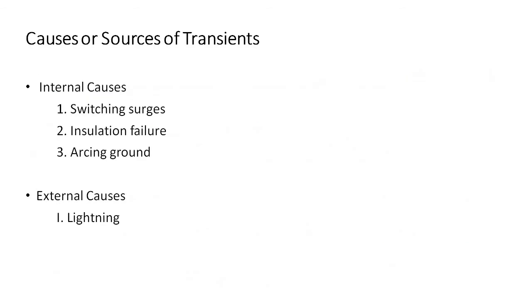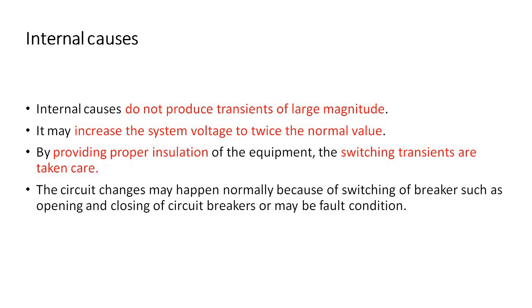Causes or sources of transients. Internal causes: first point, switching surges; second, insulation failure; third, arcing ground. Then external causes: first point, lightning. Internal causes do not produce a transient of large magnitude. It may increase the system voltage to twice the normal value. By providing proper insulation of the equipment, the switching transients are taken care of. The circuit changes may happen normally because of switching of breakers, such as opening and closing of circuit breakers, or maybe a fault condition.